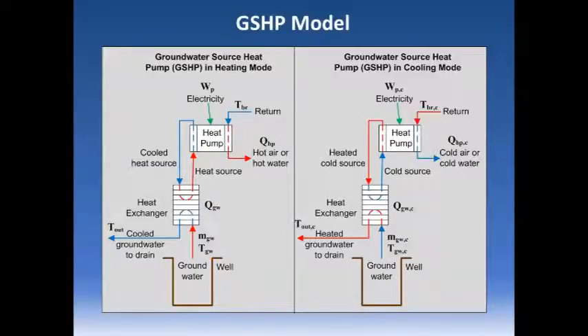Thank you for pointing that out. One other comment on the ground source system: there are two modes of operation. If you're taking heat out and putting back a similar quantity, it balances with the reservoir. However, if it's not balanced, for example if you're taking out more heat than you put back, the heat is really coming down from the surface. You can run a calculation for how much surface area you need to supply heat to the house. So when housing is less dense and yards are large compared to the houses, you have enough heat flow from the surface to make it up. But as density changes, you reach a point where it only works if you're really borrowing heat from your neighbor's yard. This is spelled out in David McKay's book also.